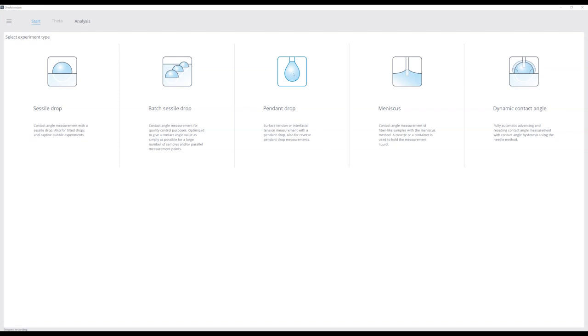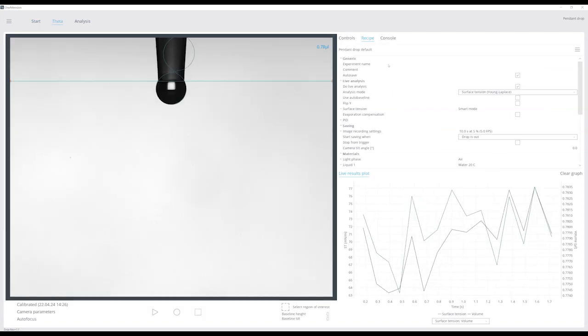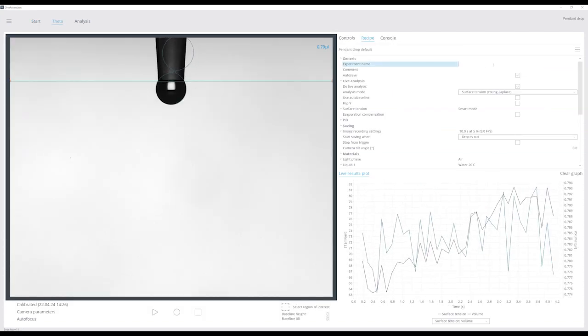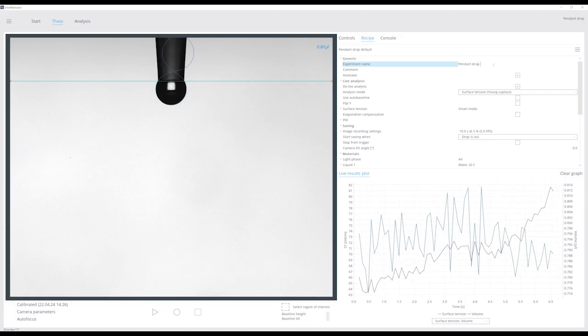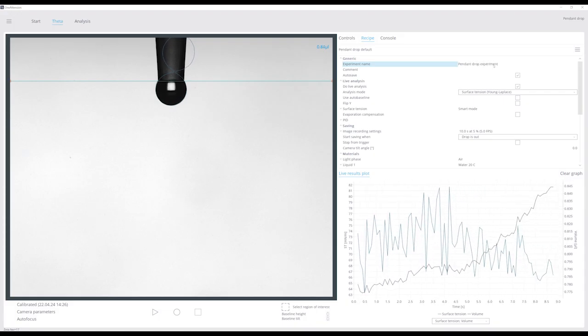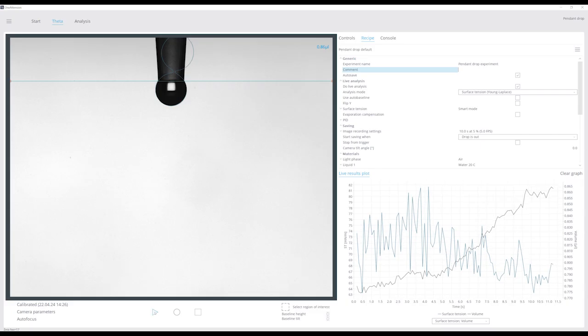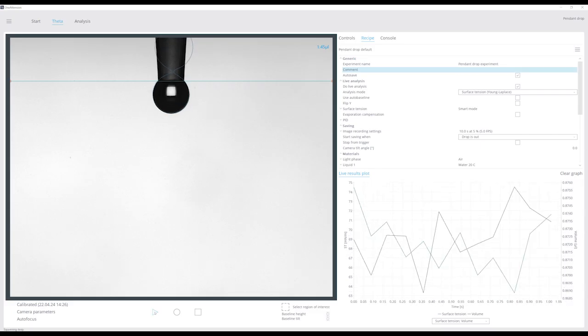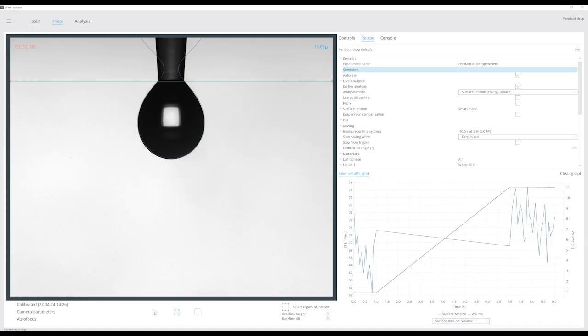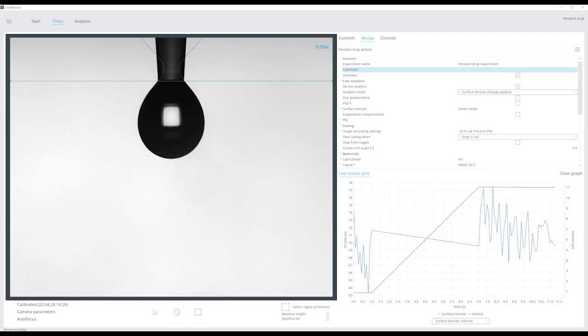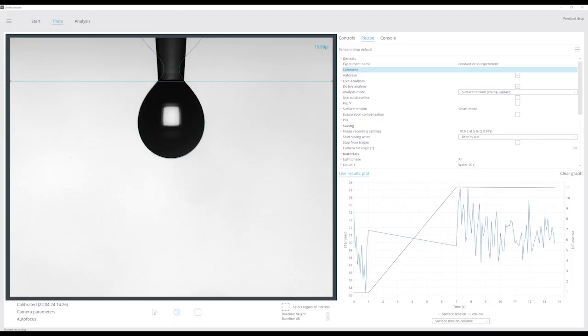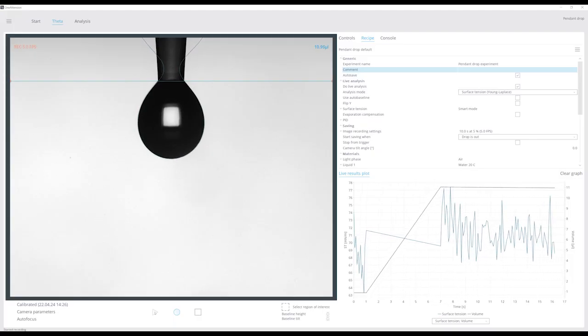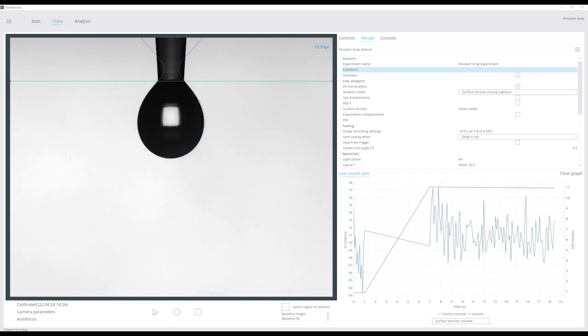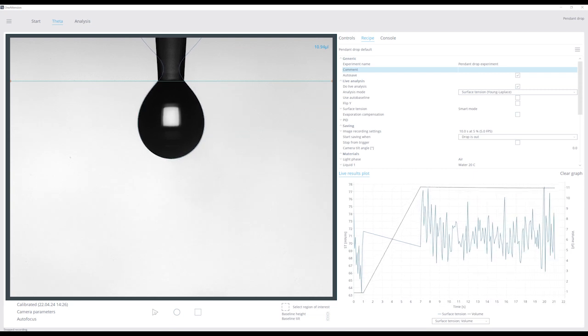Pendant drop measurements are used to determine the surface tension of the liquid. The default recipe is a good starting point for the experiments. The drop volume needs to be considered as the droplet should be large enough to gain a reliable surface tension reading. The maximum volume of the drop is dependent on the size of the tip used as well as the surface tension of the liquid. The correct volume for your solution can be found by testing. When the target volume is known, the measurement is extremely straightforward as the measurement is conducted automatically by the click of a start button.